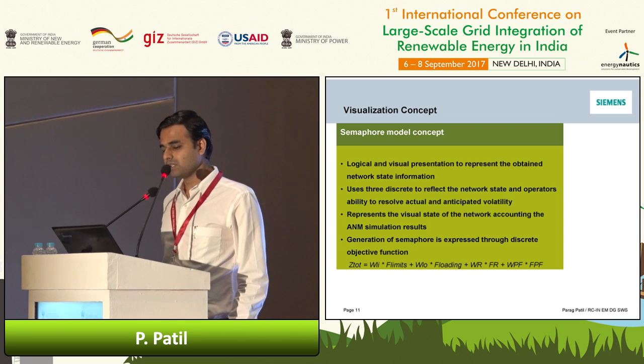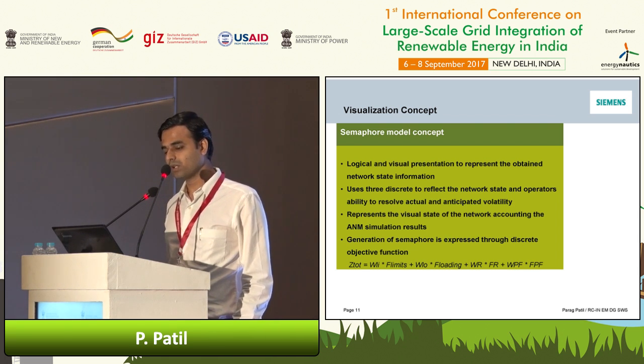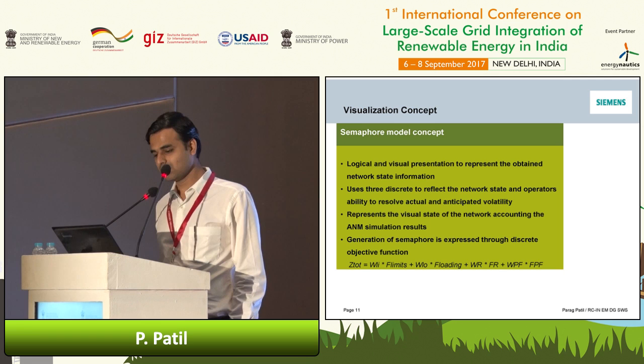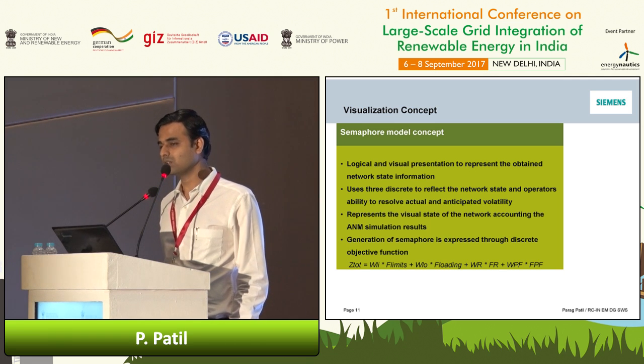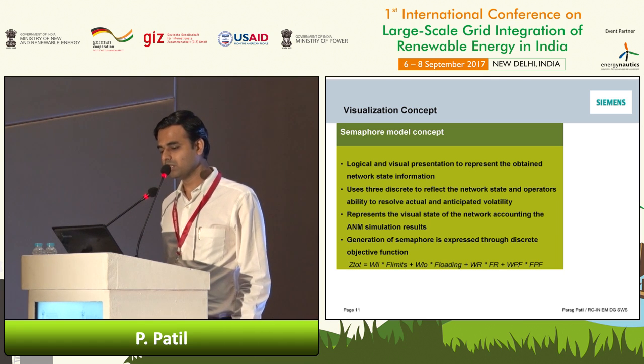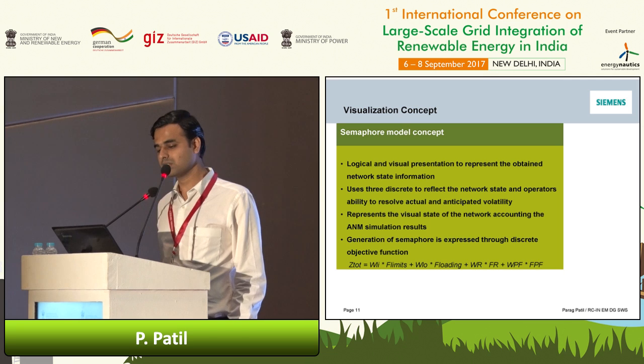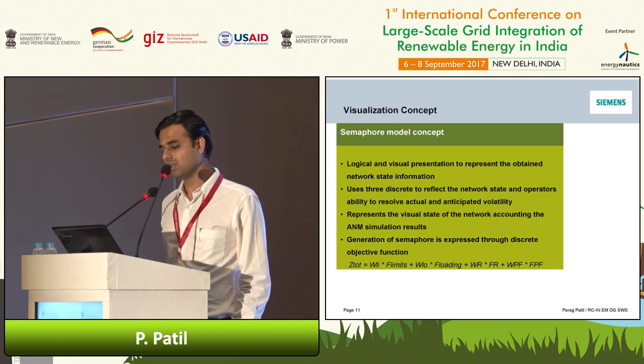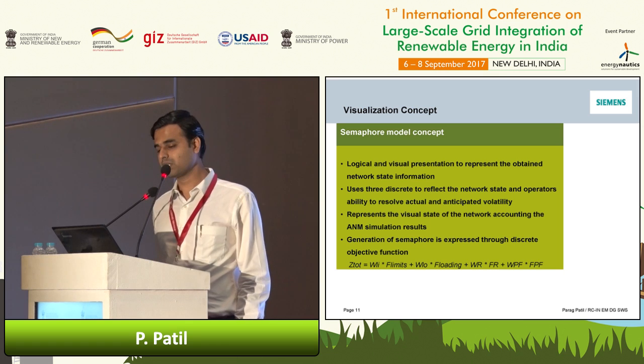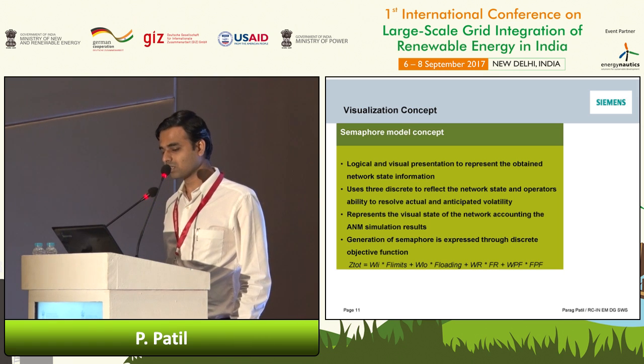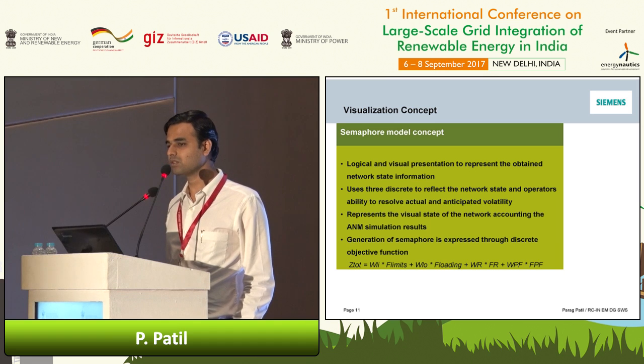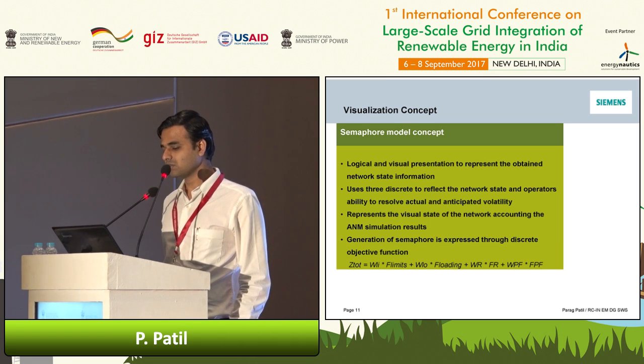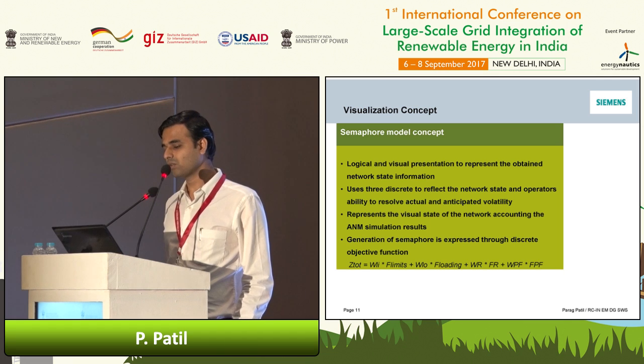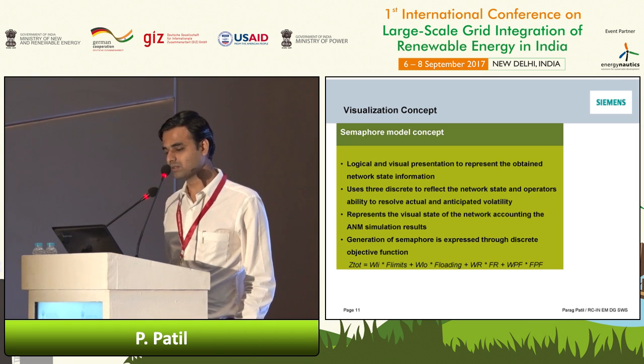Here we present one objective function called ZTOT, which gives you significance of the existing limits reached, the loadings reached, and also the reserves used by the system. F limits represents violations in your lines. Loading represents overloading in your transformers. FR represents your used reserves, and FPF is the penalty for your power factors.